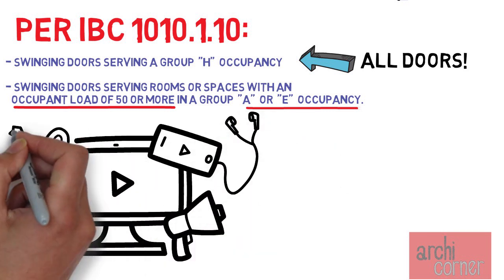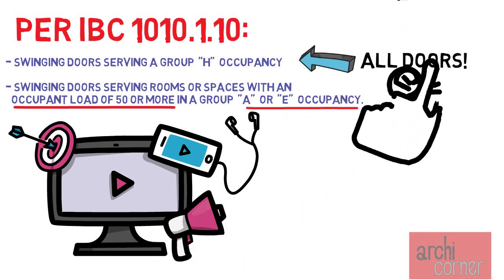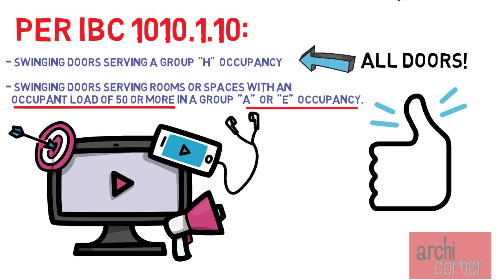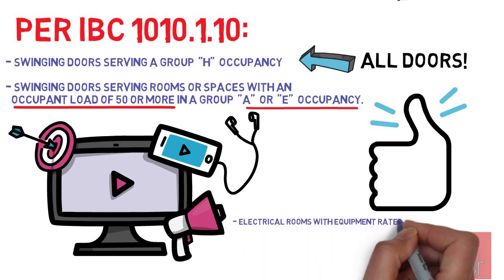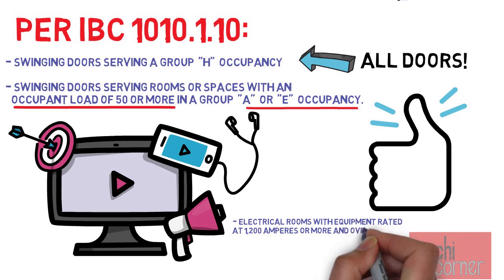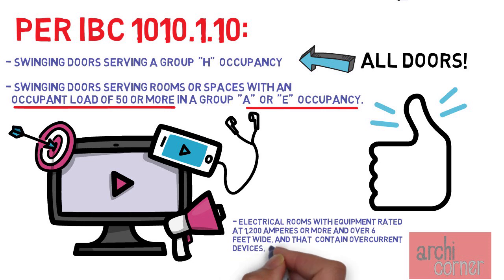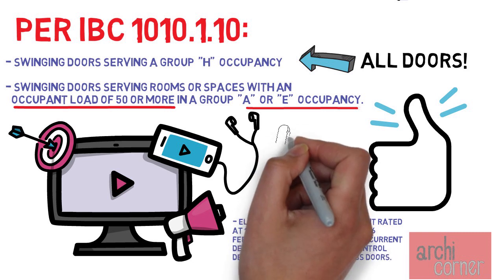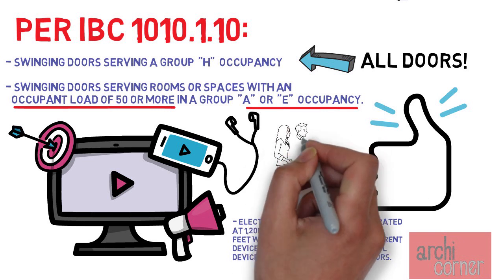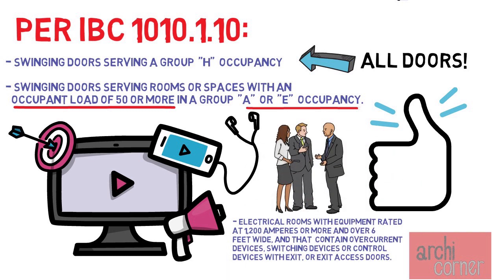If you don't know much about occupancy groups, I have made a video you can view for more general details. Besides occupancy group, this section also states that panic hardware is required in electrical rooms with equipment rated at 1200 amperes or more and over six feet wide, that contain overcurrent devices, switching devices, or control devices, with exit or exit access doors. Unless you're an electrical engineer you may not know if the equipment meets this criteria, so ask your electrical engineer.